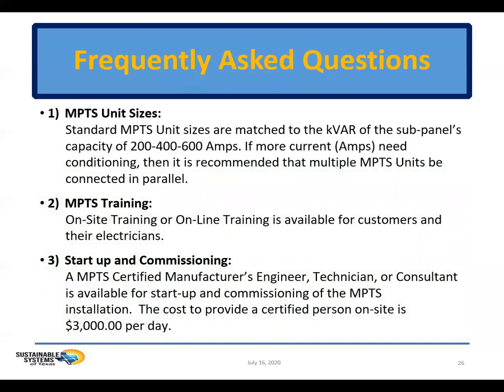So thanks, Valerie and Brian. I'm going to talk about 6 additional frequently asked questions. And the most frequently asked one is the sizing of the units again. So we just want to reemphasize that the MPTS H units are sized to match the kVAR of the sub-panel amps, being 200, 400, 600 amps, and also that it's 3-phase, 480 volts AC. Next is we often get questions on training, and so training can be on-site or online for a reasonable fee.